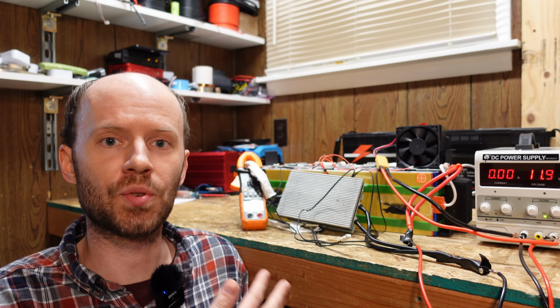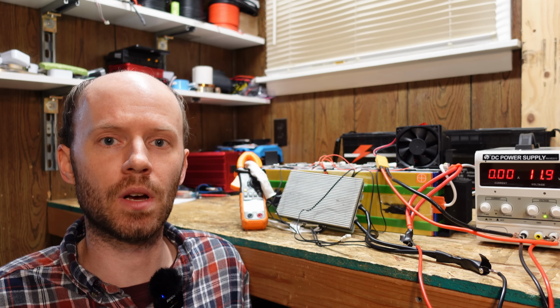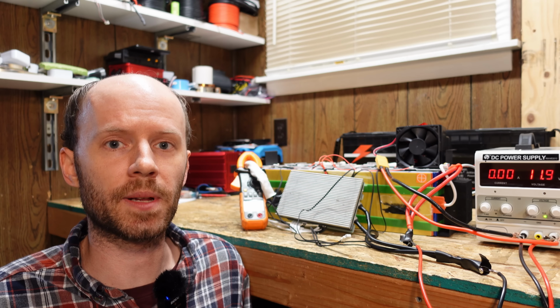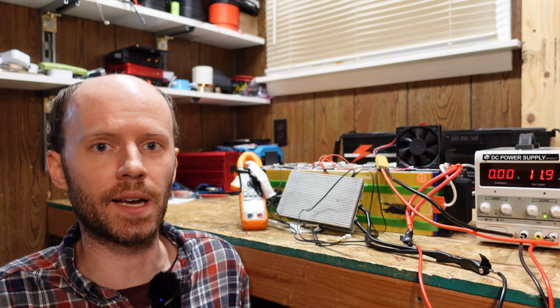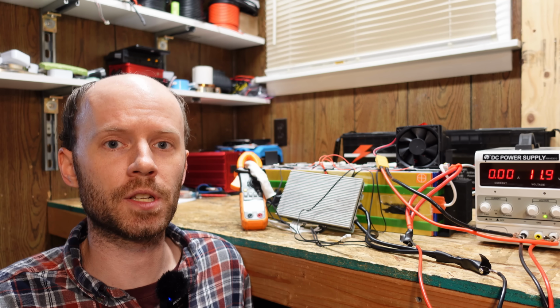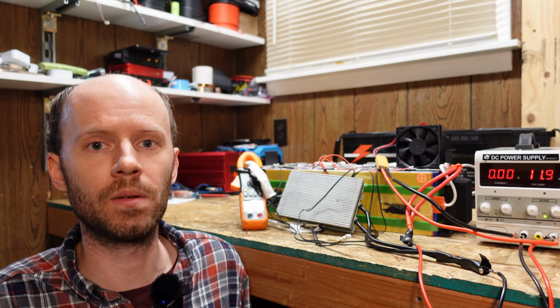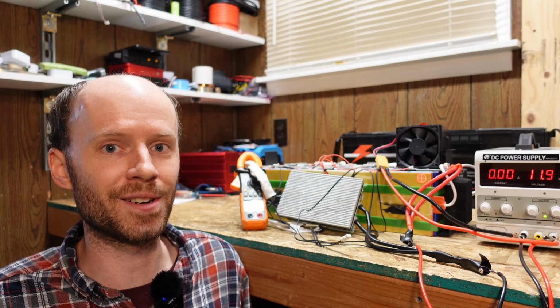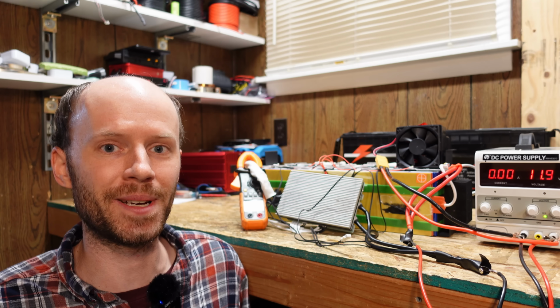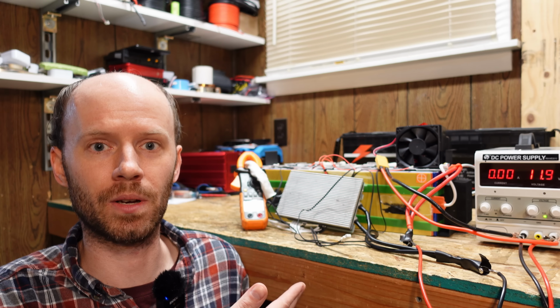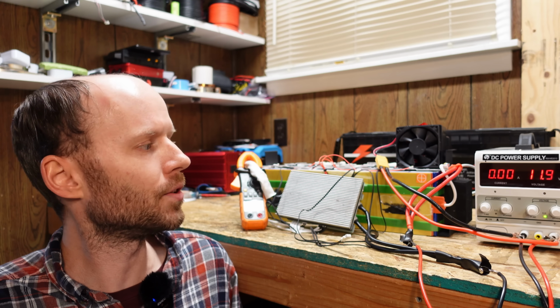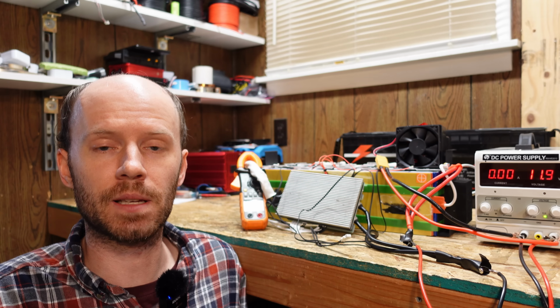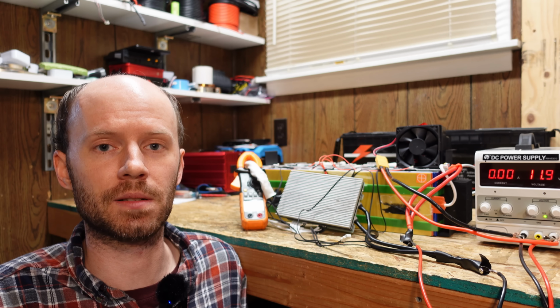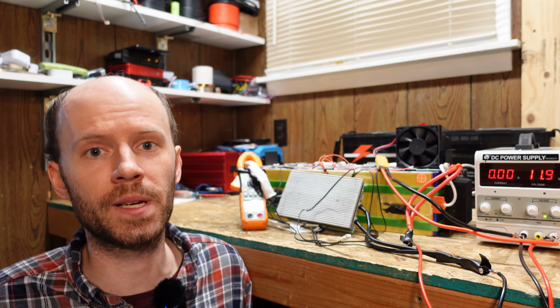So that is the quirky behavior I was talking about. I don't know why it's dropping the load when you stop charging. That makes no sense to me. In a standard solar application, this can happen many times throughout the day. Just think if I have a charge controller charging at 20 amps, and maybe I have an inverter with a 10 amp load, and a cloud moves in front of the sun or something, and that charge controller cuts out for a little bit, this BMS is going to drop the load. That just seems odd to me. I don't know if that's a defect in the BMS. It seems to be operating perfectly, so I'll assume that's based on how it's designed. Now it's not related to a thermal event because we're nowhere near where that heater should be turning on or where it should be cutting off charging.